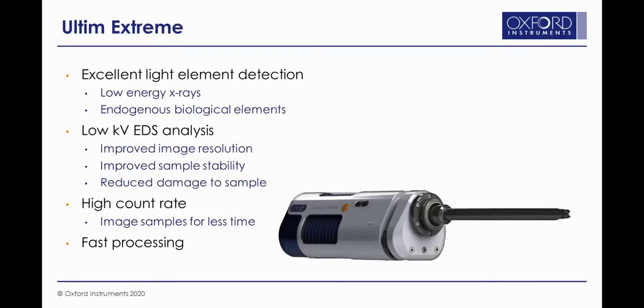To summarise, the Ultim Extreme detector has excellent light element detection, ideal for low energy X-rays and endogenous elements in biological samples. Because it can detect low energy X-rays, it can operate under low kV conditions in an SEM, which improves image resolution, improves sample stability, and reduces damage to beam-sensitive specimens like most biological samples. It also maximises the count rate by having a large area detector, meaning you can image samples for less time. Optimised electronics make the system faster with much less noise, optimising the signal-to-background ratio in the spectrum and facilitating identification. The Ultim TLE is the TEM equivalent — a windowless detector for TEM.